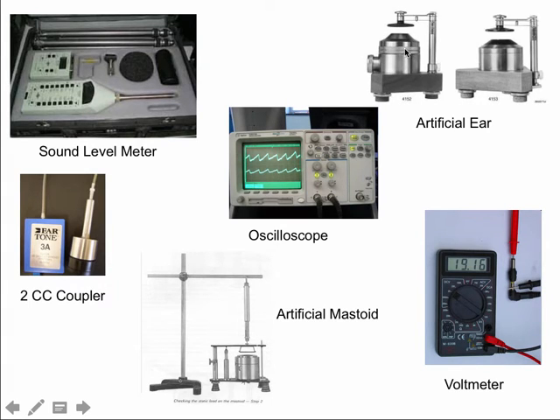So not only does it mimic the cavity space, hence it's a 6cc cavity over here that simulates the cavity between the tympanic membrane and the diaphragm of the headphone, but you also need to simulate the tension of your headphone when it's placed on your pinna, and that's what this band does. Again, things are a little simpler when you're using the insert earphone, but you still need to simulate that 2cc cavity, which is the average size of the ear canal between the tympanic membrane and the diaphragm of the insert earphone. And for adults, that approximates around 2 cubic centimeters, and that's what this cavity does.